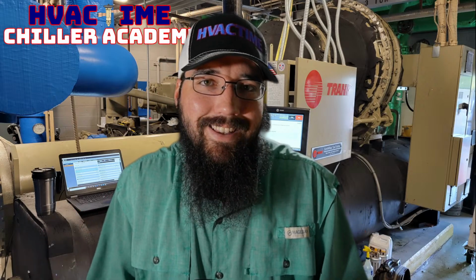All of those basic concepts are still kind of the same, and Trane has their own versions of the same thing. Now, we commonly know the low speed version, which is the CV series, CVHF, CVH, and CVD series, right? Those are single shaft low speed machines, but they also have their own version of the high speeds, and their own version of the multi-impeller, multi-stage high speeds, using helical bull gears to do all that. This is just basic fundamental starting points, and then they use that same technology in slightly different ways, calling it their own way of doing it. But in reality, a lot of the basic principles still apply: it's still a bull and pinion gear, still a helical gear at that.